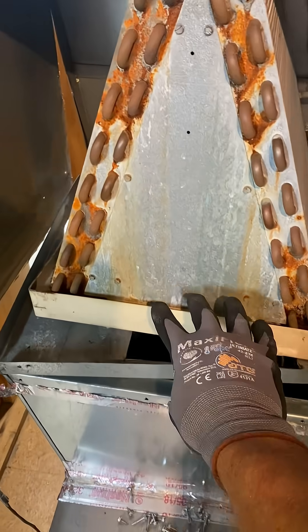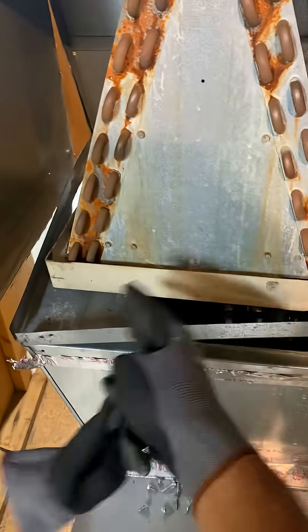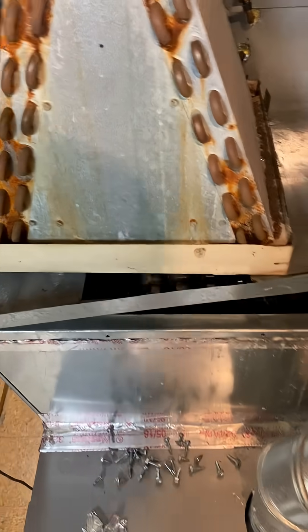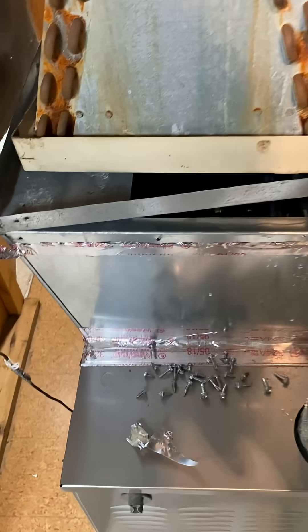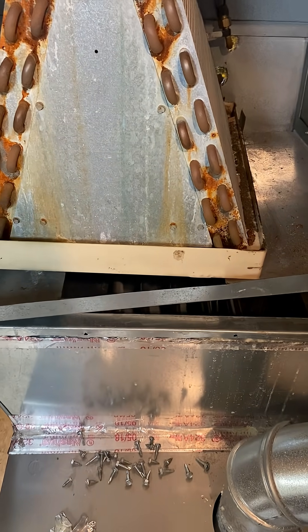So this is a 21-inch wide furnace, and then it even gets bigger. But then we shove this undersized coil in here — in terms of width — blocking off all of this airflow. You've taken a 21-inch furnace down to maybe a 10-inch wide opening. We're definitely going to blow this open all the way, full airflow through the furnace. Airflow is key to efficient heating and cooling.